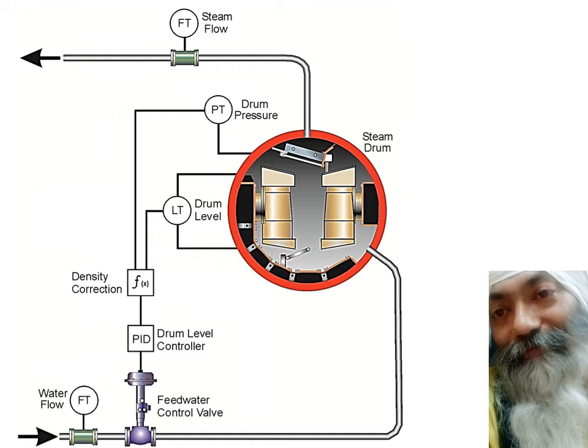And in the last session, we had seen that in case we have a boiler, for some reason, if the outflow suddenly increases, that increase in outlet reduces the pressure over here, and the reduction in pressure makes the bubble grow in number as well as in size, resulting in increase in level for a short period of time, and this process is known as swelling.